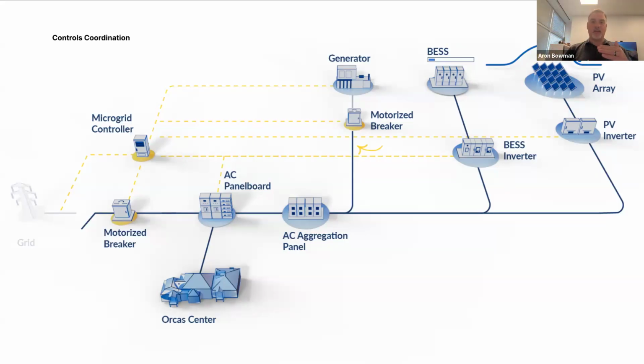If the loads at the facility are lower, with a traditional generator run you would run the generator at a lower efficiency, which is often referred to as lugging the generator. We'll apply load from the battery energy storage to bring that up so the generator is running at, say, 65% or 70% efficiency, which is where you get the best fuel usage.